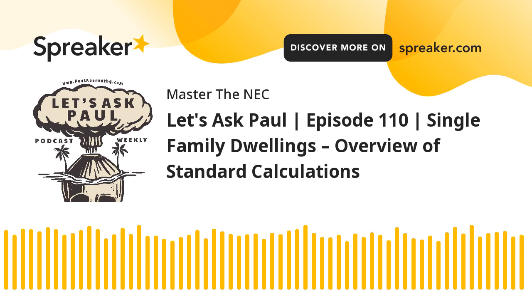All right. So when it comes to the cooking, you're going to look at it and you're going to either use column C, or if it falls under A or B, then you can use those values and you have to compare those to column C, and you can take whichever is the lesser. Okay. Now, if you're over 12 kW for a range, for example, then that's when you're going to use note 1 or note 2, okay, for that application.